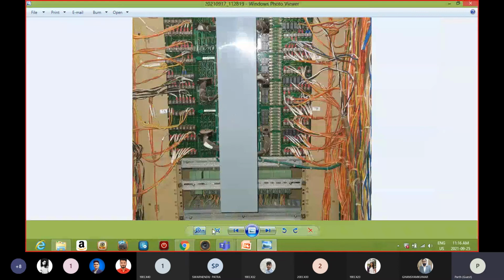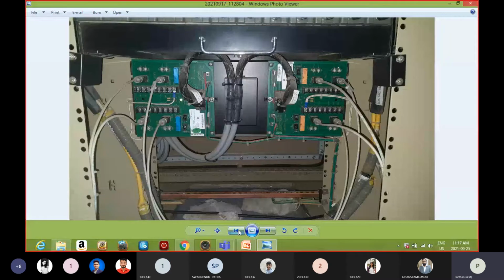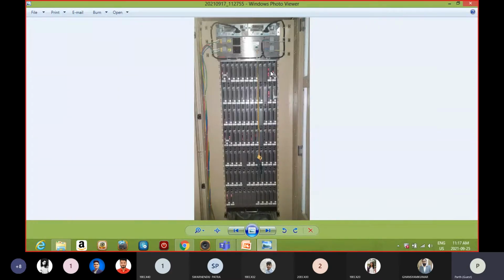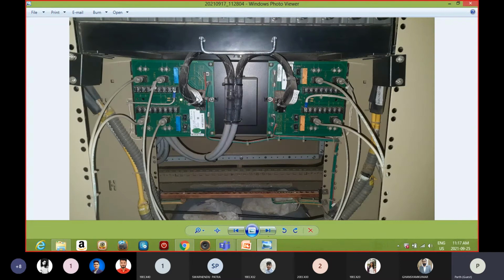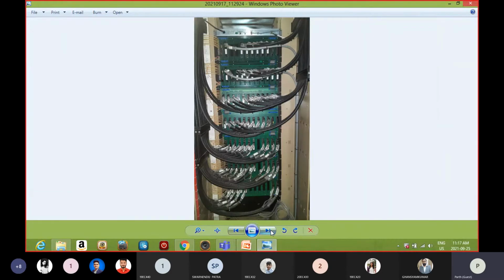Again, let me explain how the panels are connected. This cable is coming from behind these communication cards. The cable from behind this communication card will come here, and through this coaxial cable all the panels are connected, forming what we call the control net. Through this control network, all the data will transfer from one panel to another panel, and also to the HMI.